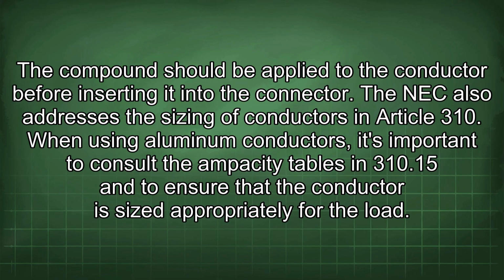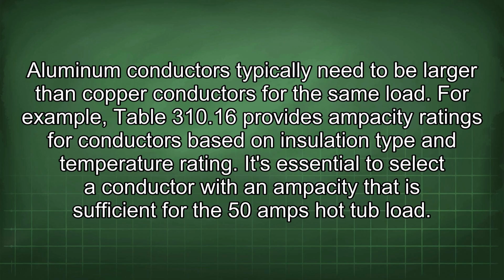The NEC also addresses the sizing of conductors in Article 310. When using aluminum conductors, it's important to consult the ampacity tables in 310.15 and to ensure that the conductor is sized appropriately for the load. Aluminum conductors typically need to be larger than copper conductors for the same load. For example, Table 310.16 provides ampacity ratings for conductors based on insulation type and temperature rating. It's essential to select a conductor with an ampacity that is sufficient for the 50 amp hot tub load.